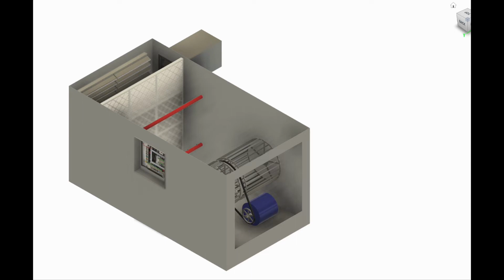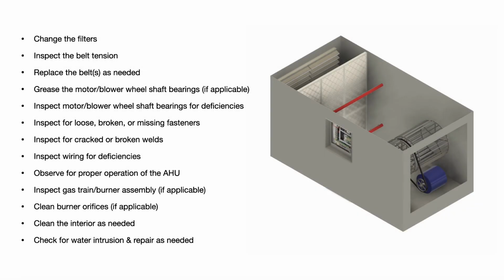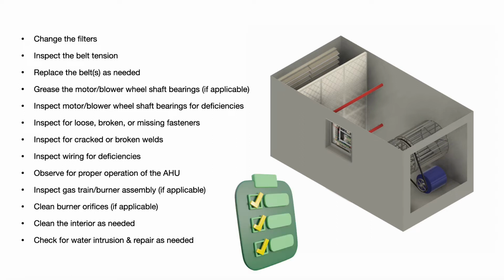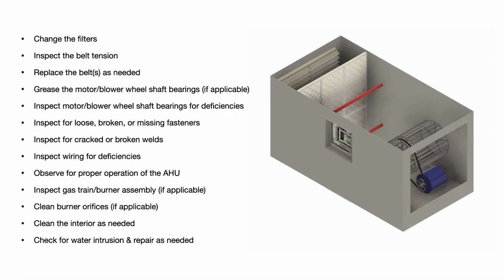Now let's talk about maintenance. Safety first. Be sure to turn the power off, practice lockout, tagout, and wear proper PPE like safety glasses, etc. So this will be a high-level overview of the generalized maintenance tasks that need to be performed on an air handling unit, sometimes referred to as an AHU. You want to change the air filters, ideally every 3 months, depending on the type and size of air filters, maybe more often, maybe less often.